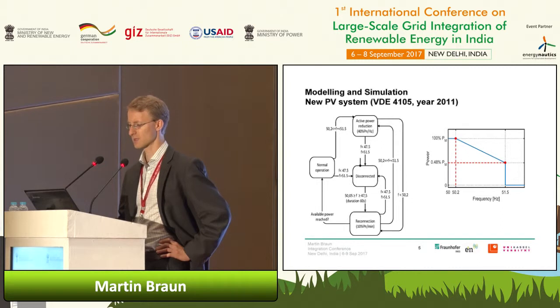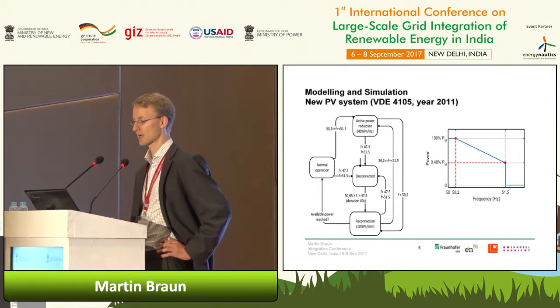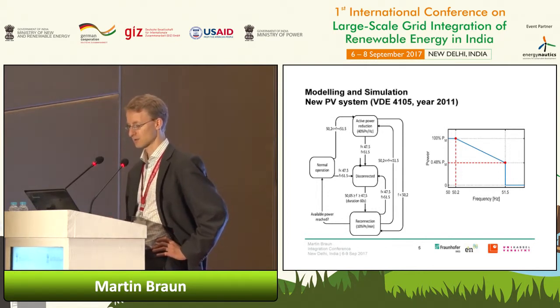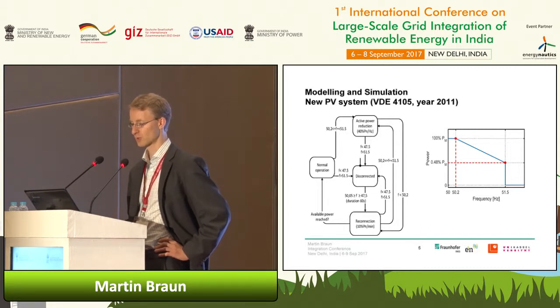So depending on the state, we have state changes. You can see that if we are in normal operation, then what happens for the PV system if it's in over frequency, so larger than 50.2 Hertz, is that it's going to dynamically reduce active power. In case the frequency is out of the band, it's going to be disconnected. Then if it's within a certain bandwidth, it can be reconnected in case it was disconnected. And so you see you can jump between the different states.